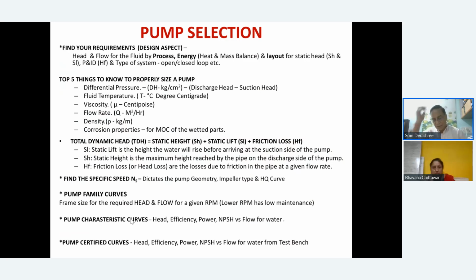Normally, you have a process diagram, and from there you try to arrive at what the flow is, for some typical heat exchangers or some columns, etc. So you will get to know what the head requirement and the flow requirement will be. Through a process and energy balance, you do heat and mass balance to work out what the cooling water requirement is, and so basically you can arrive at the design aspects of it. And then the layout of the typical building, like you may need a barometric leg, if you have a vacuum system, so you need at least 36 feet of leg. So you have to send the water to that particular height.